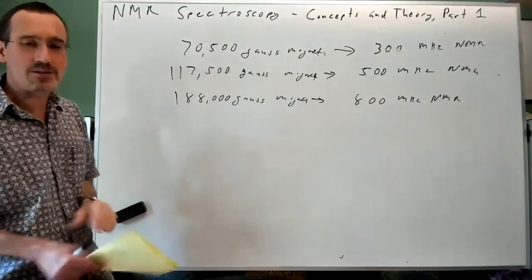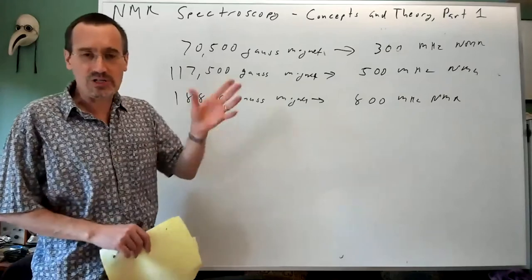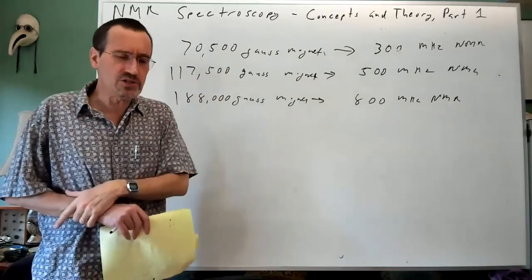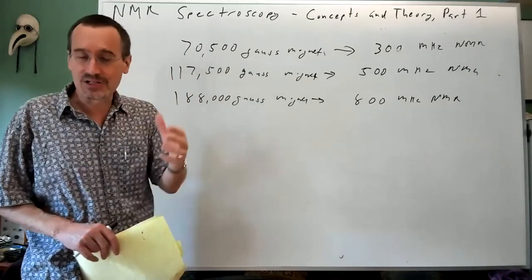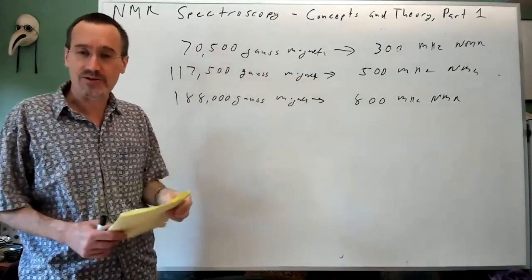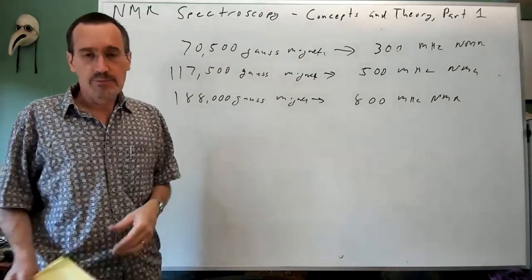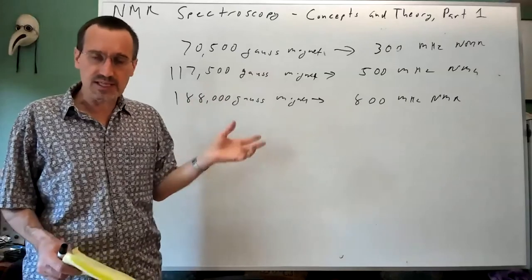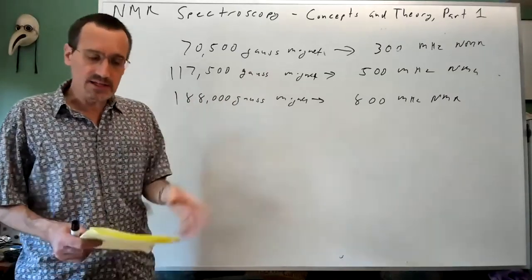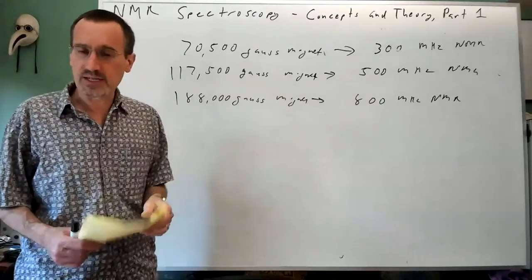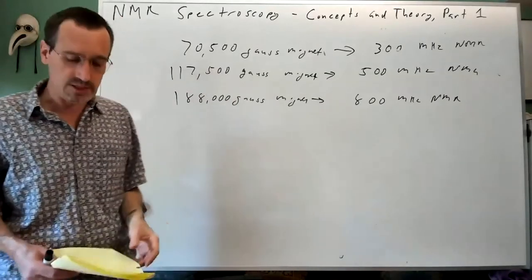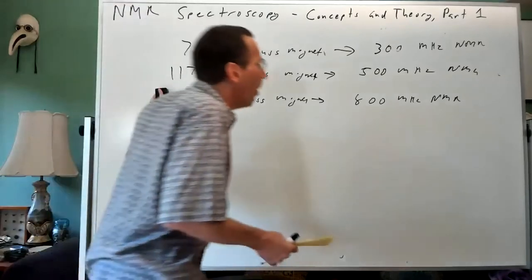NMR spectrometers push the limits of how strong a homogeneous magnetic field you can make. The magnetic field has to be homogeneous so that the sample in the top of your NMR tube experiences the same magnetic field as the sample in the bottom. If you had a non-homogeneous magnetic field, you wouldn't get a peak, you'd get a broad band that would be too broad to see.